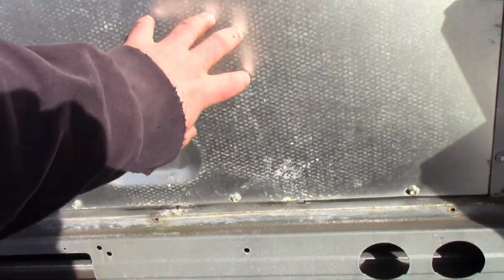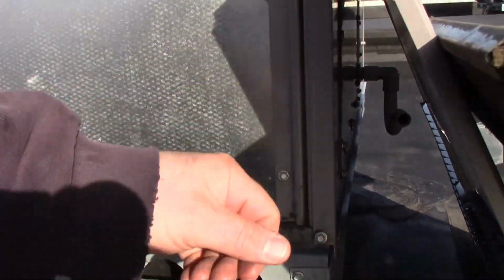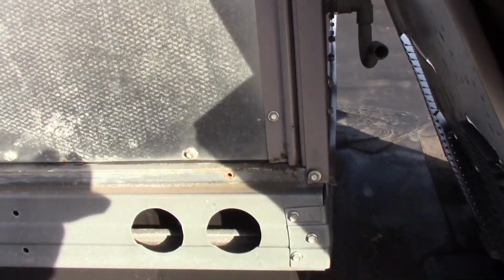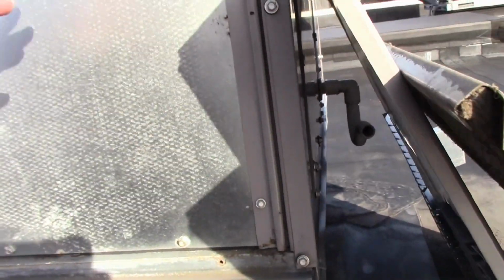So what I'm going to do too is I don't need to take this entire panel off to check the heat exchanger, really. I just need to take this outside panel off here. It's easier to see the bends at the end, and that's usually where they're going to break. Judging by that inside wall, we're not going to have an issue with it, but because we're here and because I want to be thorough, we're going to take a look at the condition of the heat exchanger.